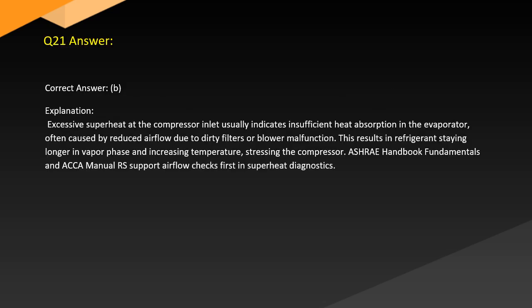Answer. Correct answer: B. Explanation. Excessive superheat at the compressor inlet usually indicates insufficient heat absorption in the evaporator, often caused by reduced airflow due to dirty filters or blower malfunction. This results in refrigerant staying longer in the vapor phase and increasing temperature, stressing the compressor. ASHRAE Handbook Fundamentals and ACCA Manual RS support airflow checks first in superheat diagnostics.